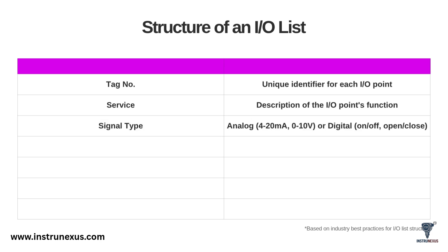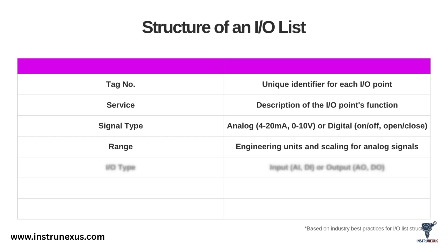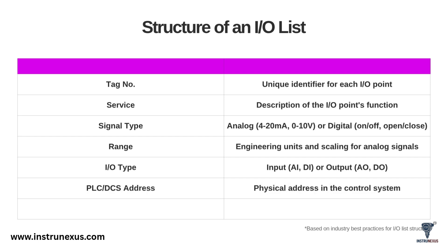Signal type is critical – is it an analog signal like 4-20 milliamps, or a digital signal like an on-off contact? Range, for analog signals, defines the engineering units, like 0-100 PSI. IO type classifies the point as an input (DI or AI) or an output (AO or DO). PLC/DCS address is the specific physical address in the control system – the exact channel, card, and rack where the signal will be wired. Remarks is a catch-all for any special requirements or notes.